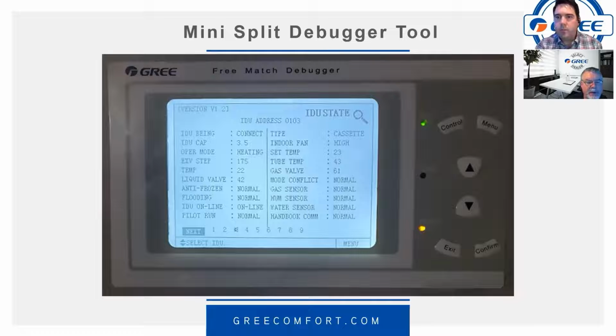Yeah. And you can see a lot of different values here. It's telling you the operating mode, where the EEV is. It's at the 175th step, so fairly tight, right? If 0 to 50 is considered closed and 480 is considered fully open. And the temperatures and things are displayed in Celsius. We're sorry about that, but that's what we got.